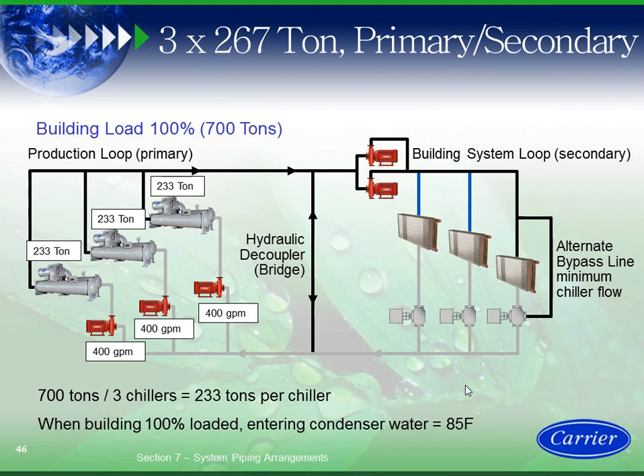So let's look at the schematic on this. Again, 100% load point is 700 tons. So I have 3 machines in parallel delivering 233 tons apiece. Okay, and what this engineer was looking at was running 3 turbo core machines because in his mind, based on the marketing, he thought this was the most efficient chiller in the marketplace. Okay, so I have 3 machines running 400 GPM delivered to each. Okay, primary, secondary system, and if one machine goes down, I could deliver my 525 ton minimum load.